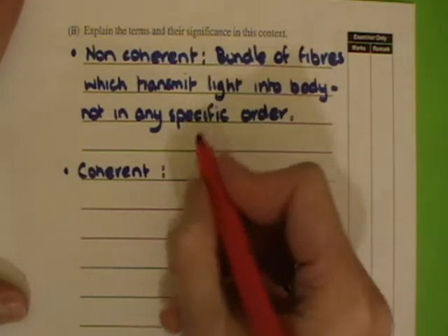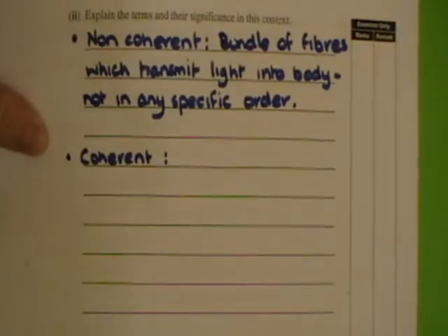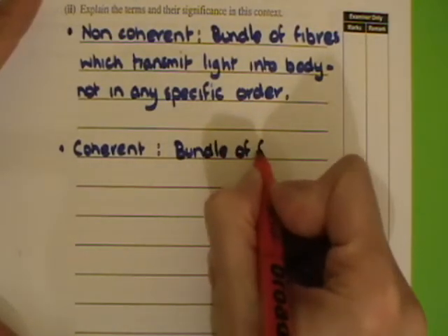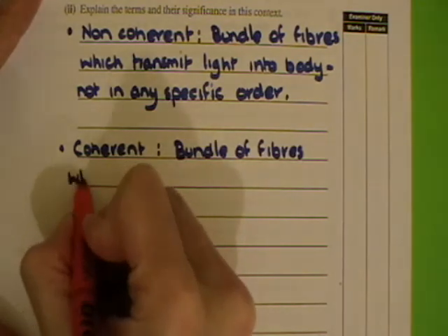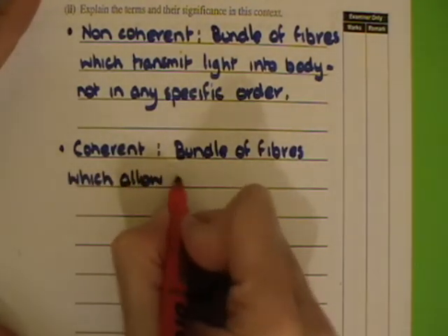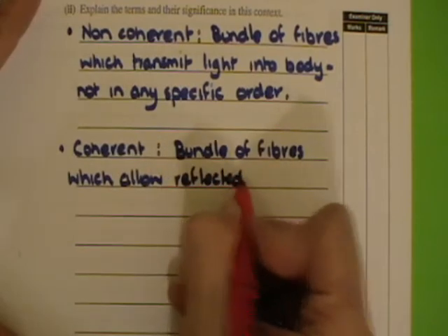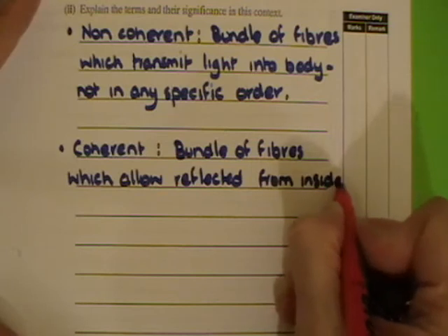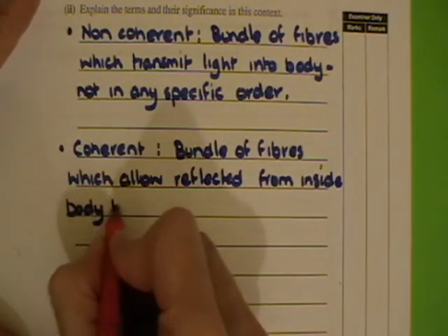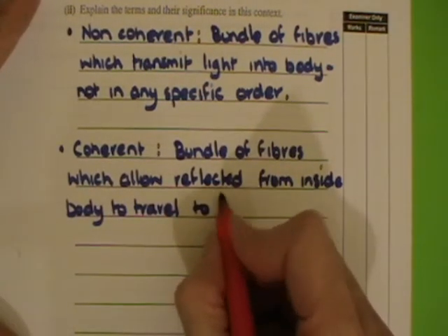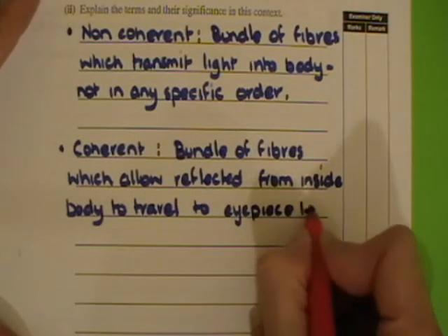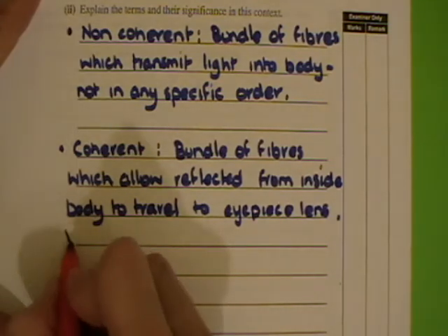Coherent then — and note the quality of written communication marks here, so be careful that you're writing in proper sentences. The coherent bundle is a bundle of fibers which allow reflected light from inside the body to travel to the eyepiece lens. They are very carefully ordered.